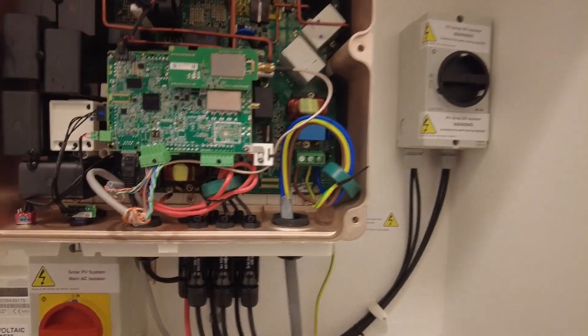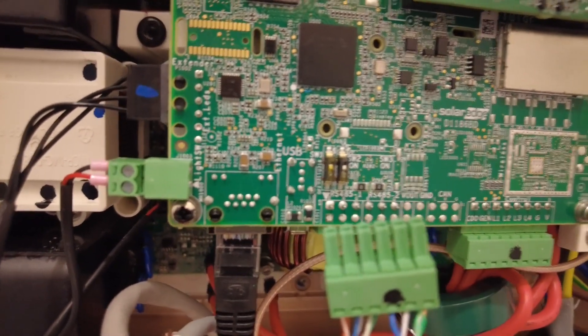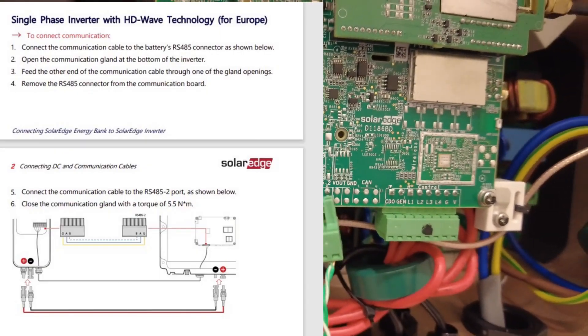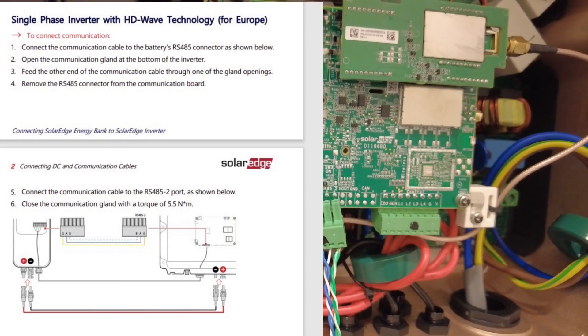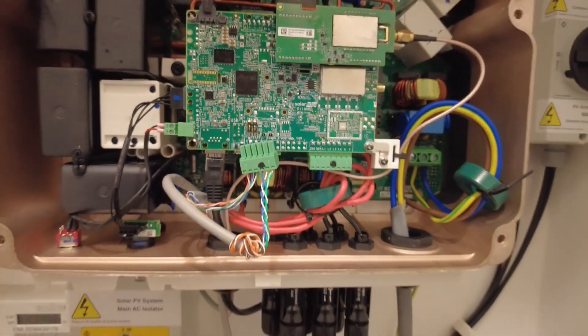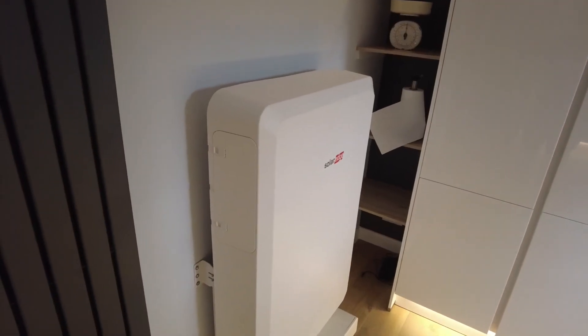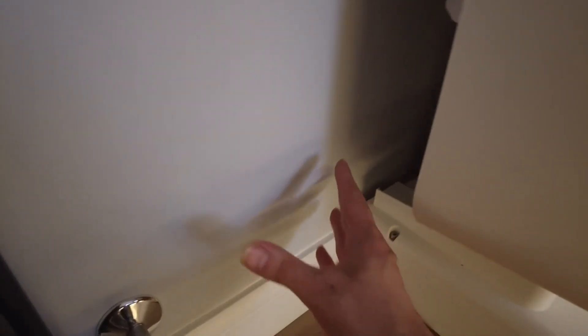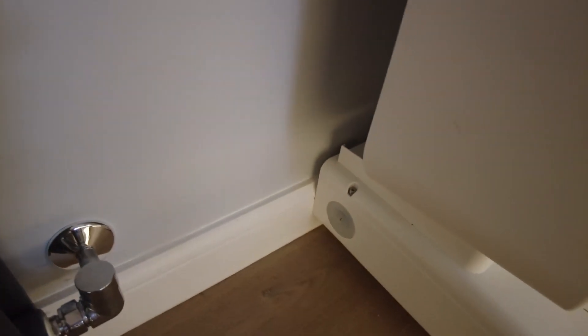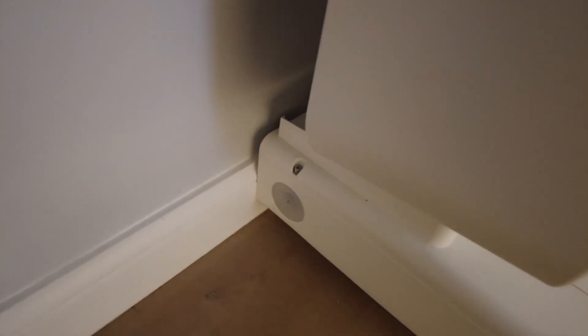For example, when it comes to RS-485 comms, there are two dip switches here that need to be set — one for the left-hand side, one for the right — and there's no description in the manual saying you need to set the dip switches for the metering to the battery. I'm hoping this will be resolved, otherwise it could be a replacement communications board. On a positive note, my installer has closed up the outer side panel very neatly. I was expecting cables to be visibly going into the wall, but he's managed to drill a hole through the skirting board so you can't see the cables at all — very neat indeed.